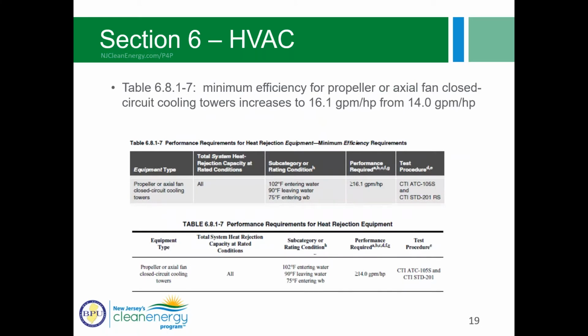All right, so this is in regards to the minimum efficiency for axial fan closed circuit cooling towers. The specific efficiency metric for those is GPM per horsepower, and it increased up to 16.1 from 14. So it's specific to that type. All of the rest of the table remains the same.